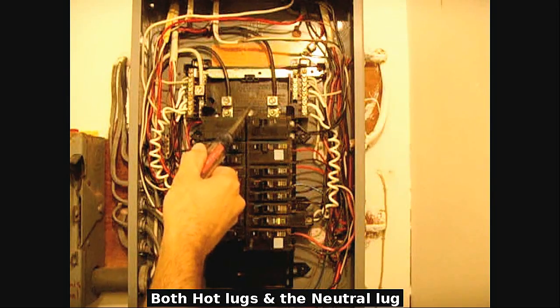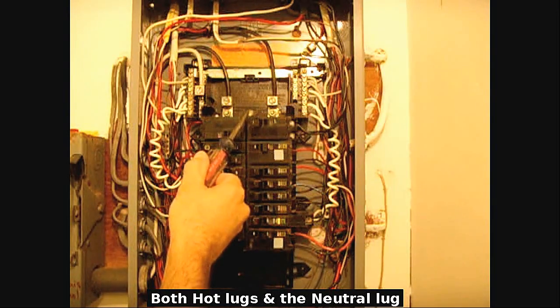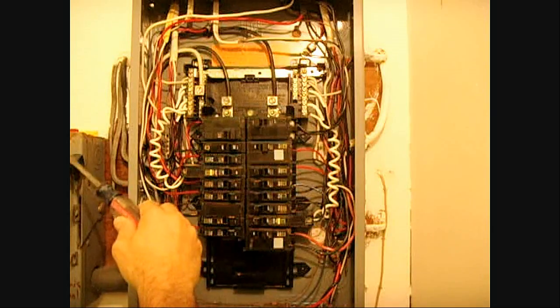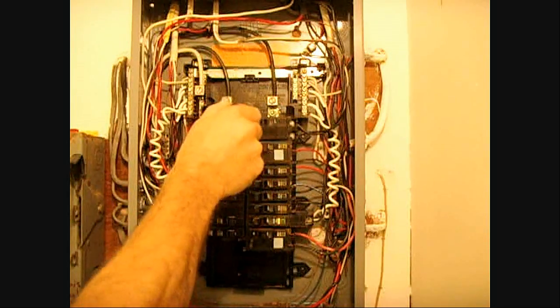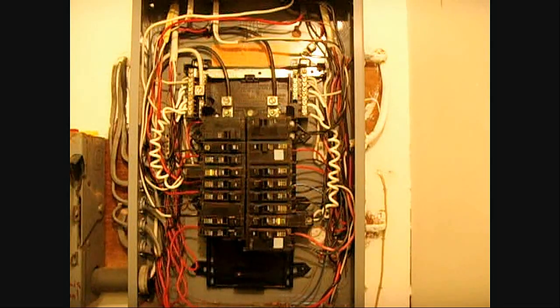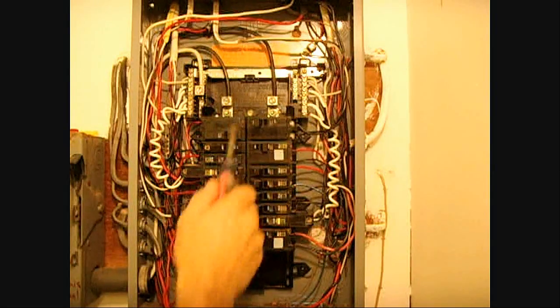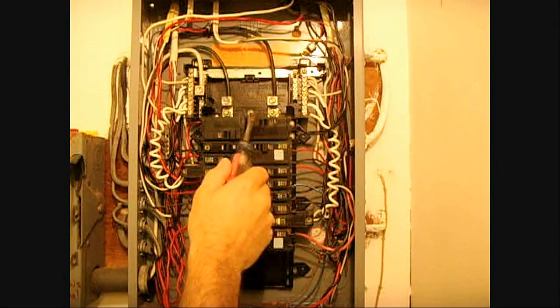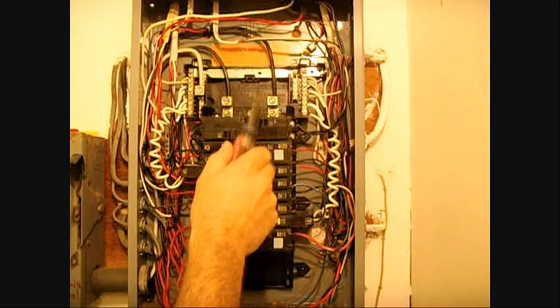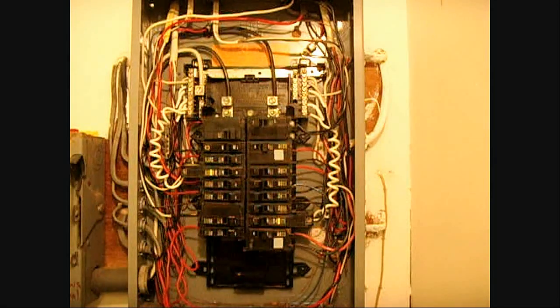If your panel is being fed from a main breaker in a different location, shut the breaker off or pull the throw switch, and then you could unscrew these. You could take a wire brush, clean the copper, clean out the lugs. You can brush some Noalox on the wire, reinstall it, and tighten it down securely.